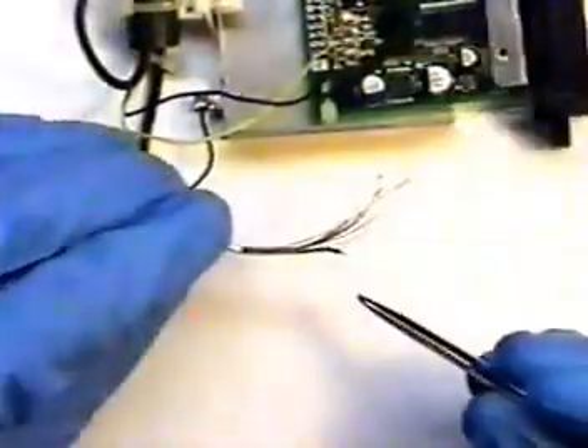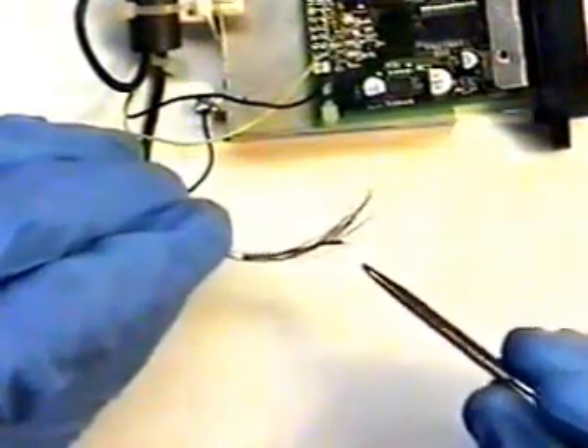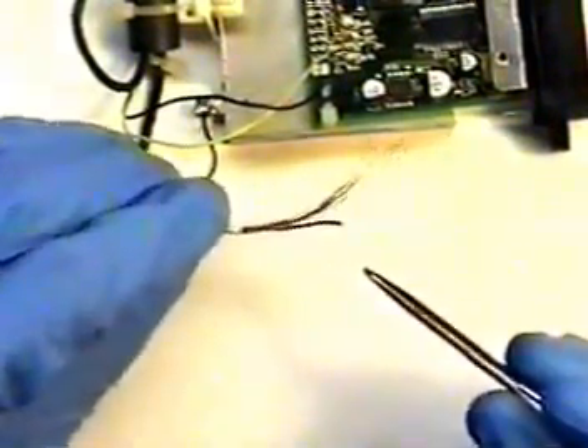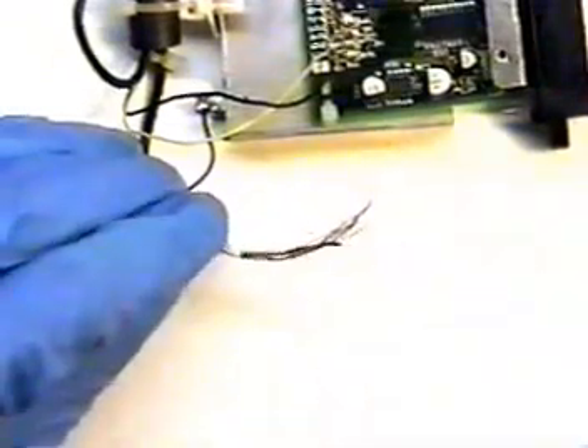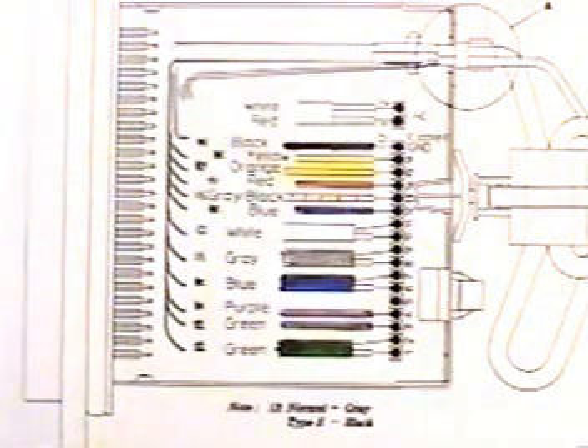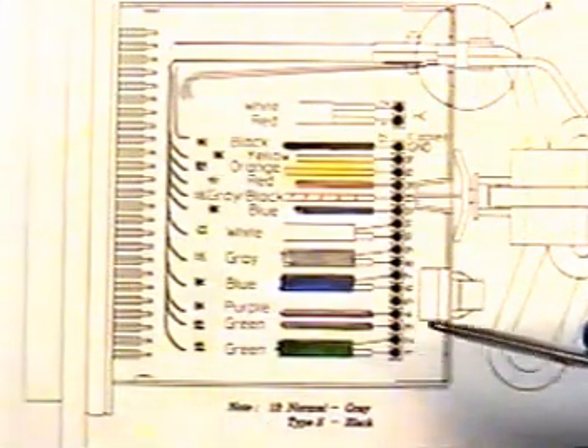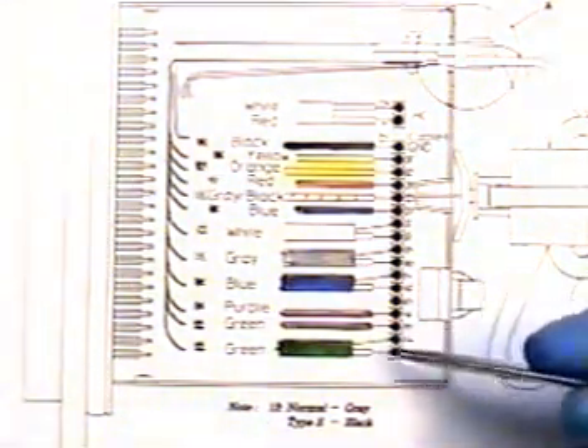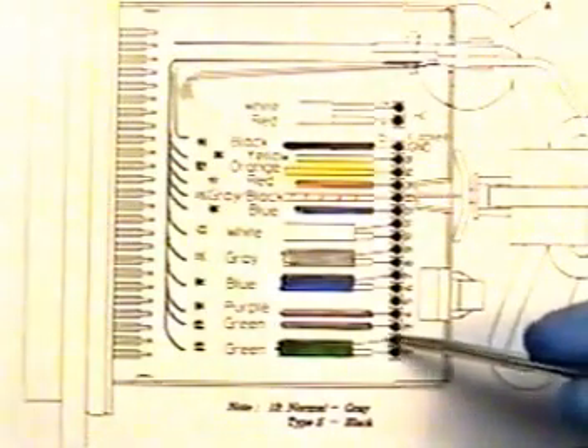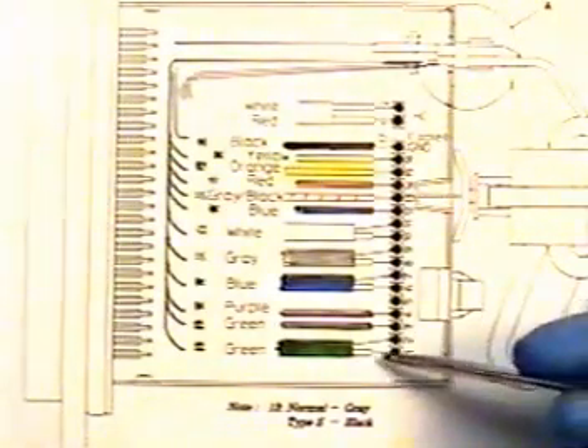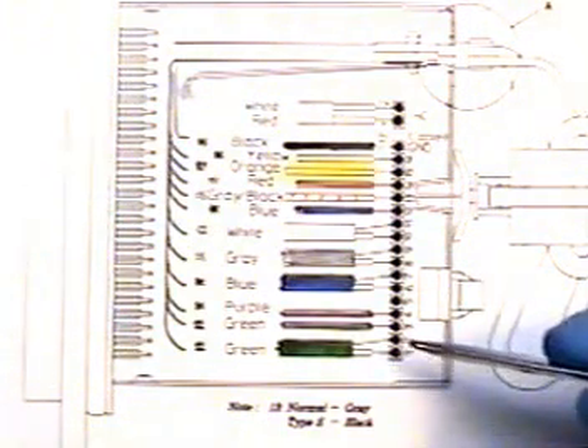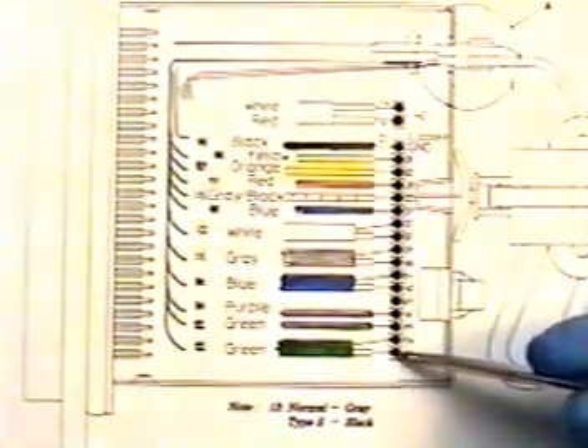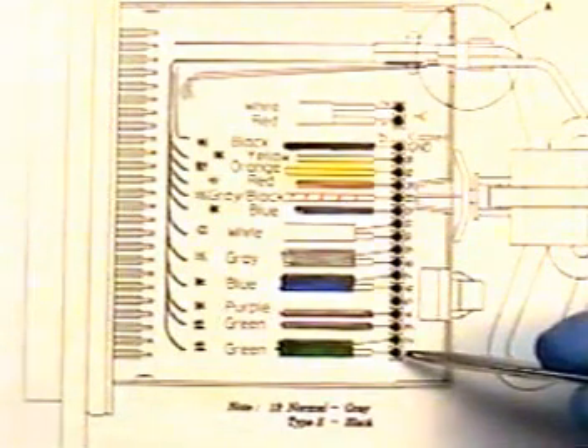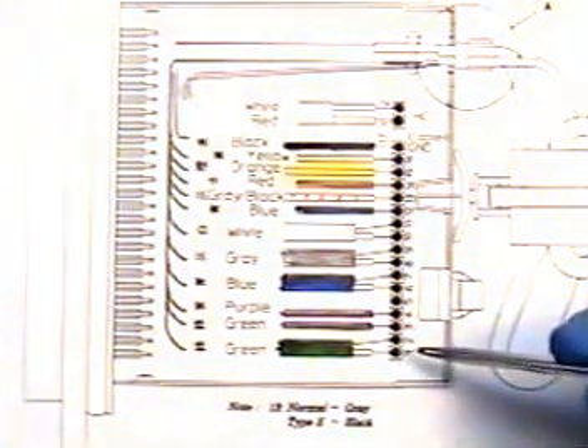You'll now need to resolder each and every color-coded CCD wire to Series 200 setup board. Due to the very small size of each wire and its color code, you will need to refer to the wiring diagram provided with this videotape. Be sure when soldering the wires that the ground shield is soldered to each point respective to the lead wire. The wire must go completely through the solder joint to the other side of the PCB board, otherwise no video will come through CCD.